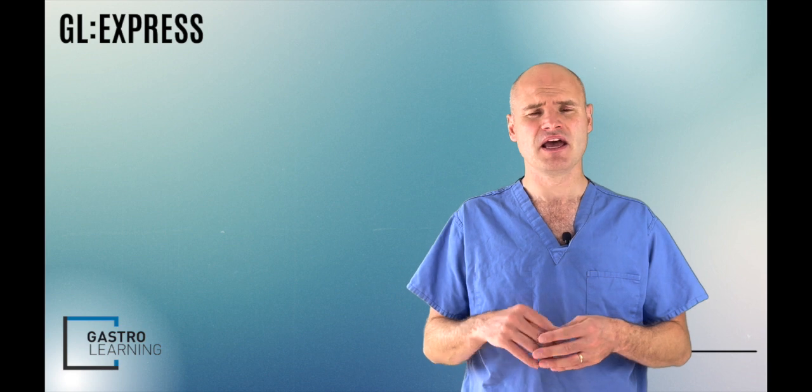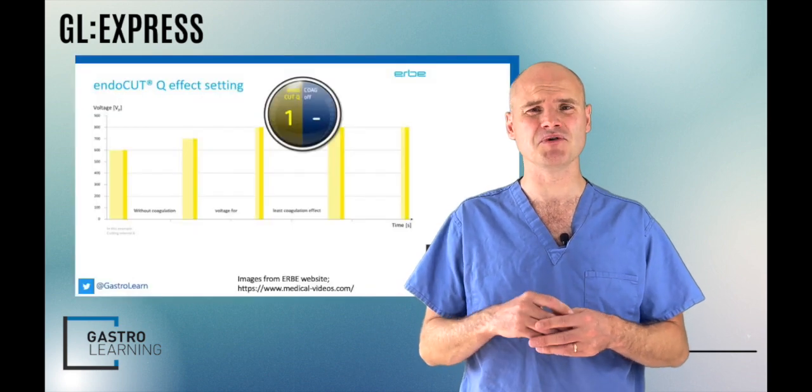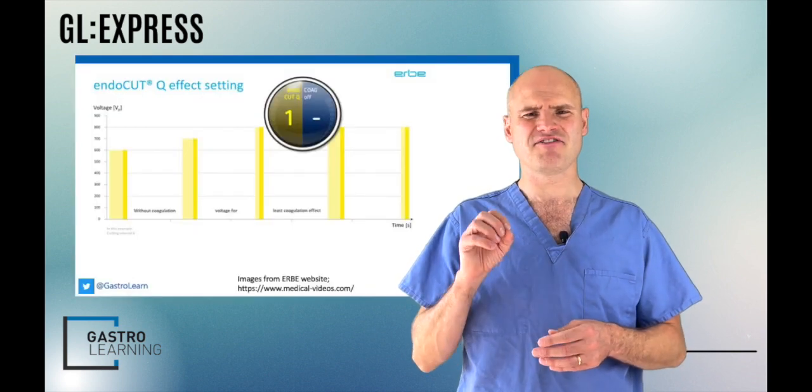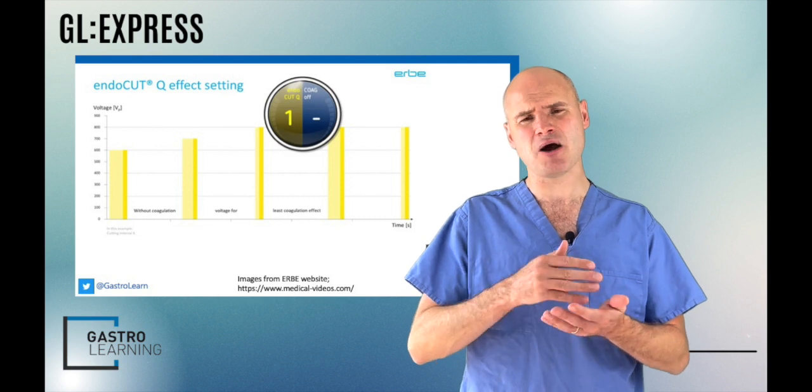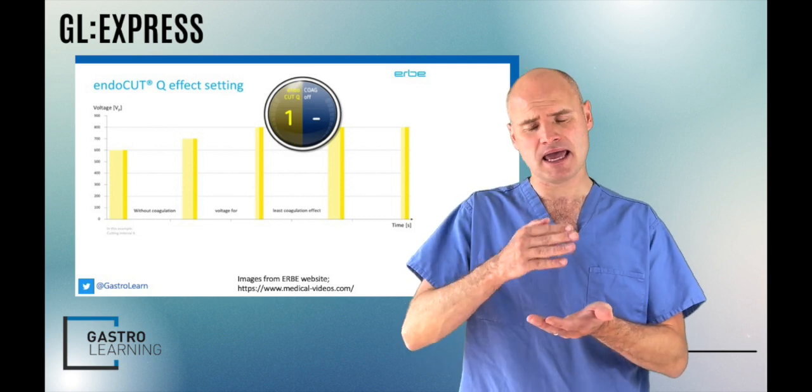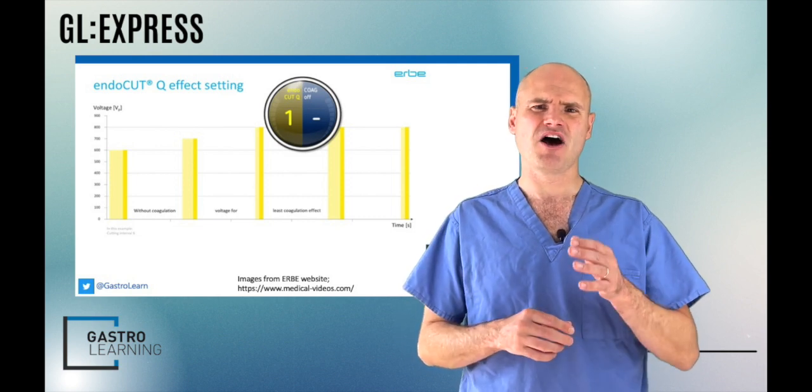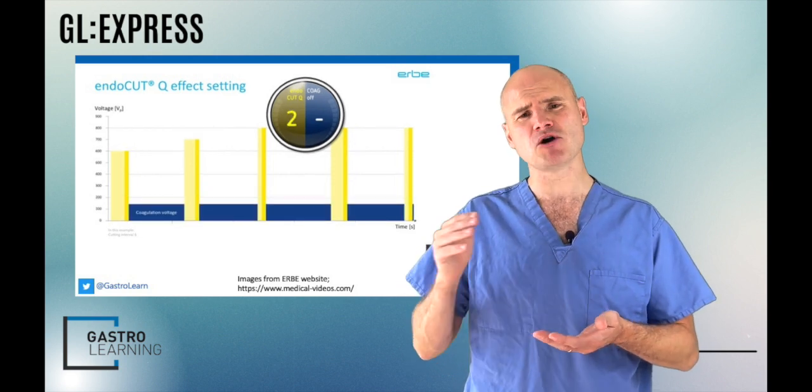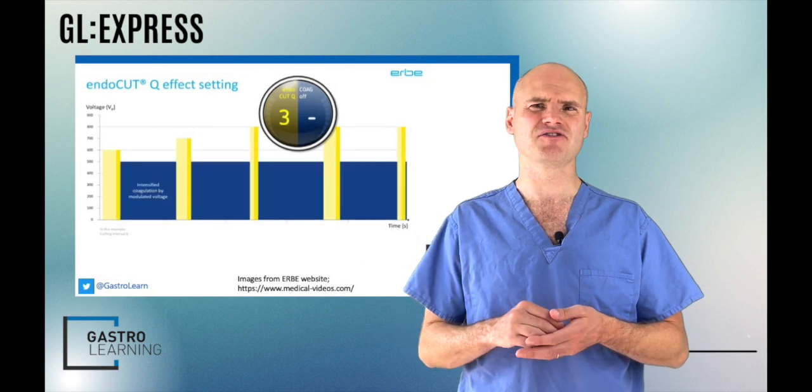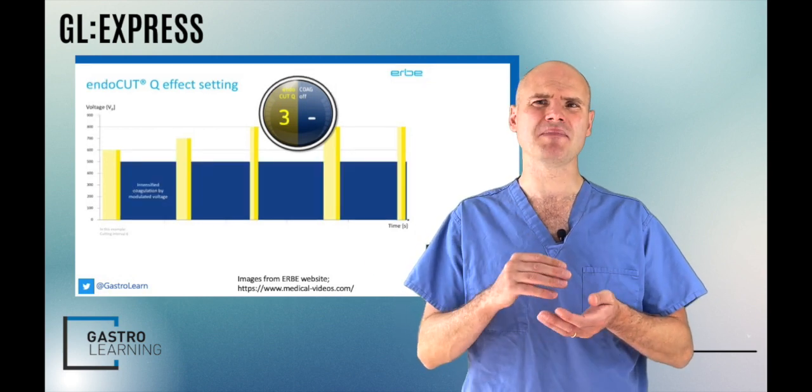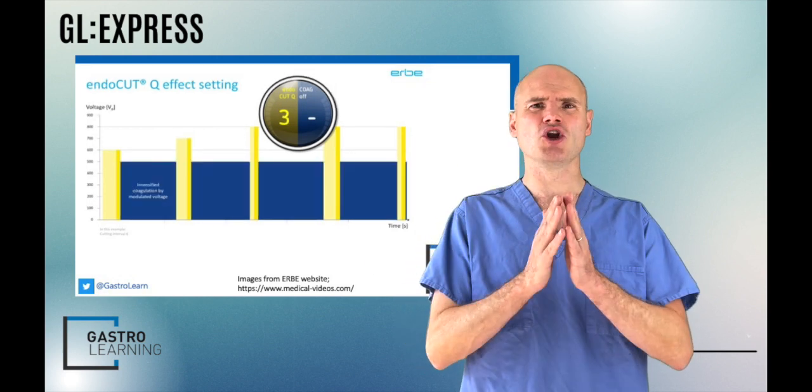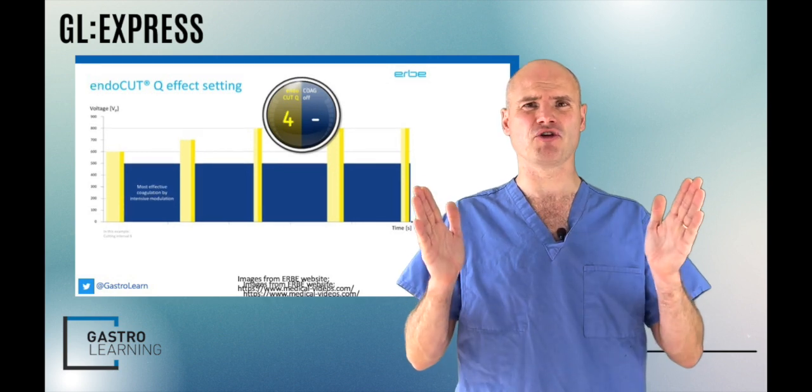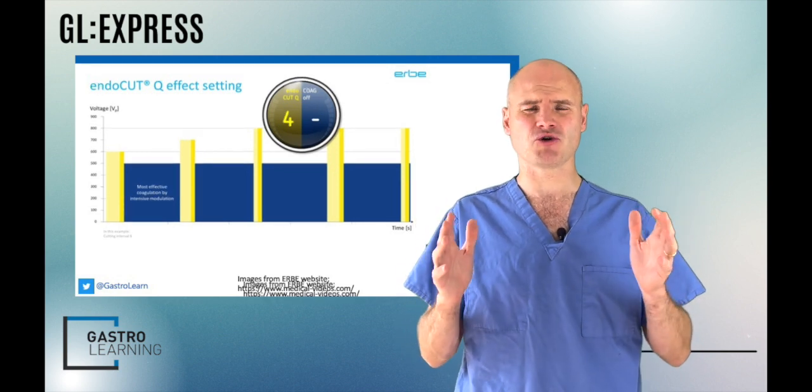Next thing you have to select is the effect. There are four different effect settings numbered one to four. The effect setting is you choosing how much coagulation you want there to be in between your cuts. Effect one has no coagulation in between the cuts, and effect four has the most coagulation. When I say most, I mean the amount of voltage, not the duration of coagulation. The duration is determined by the cutting interval I'm going to speak about later.